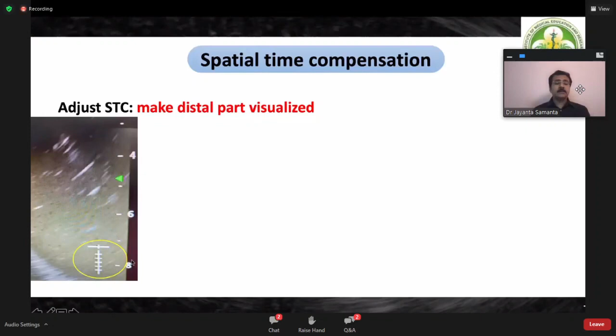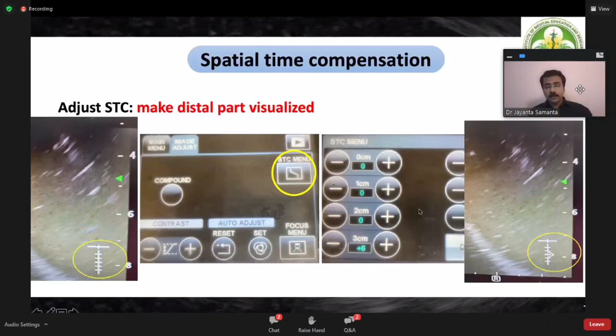So at default mode, you'll find something like this. At various depths, at 0, 1, 2, 3, 4, 6 centimeters, the setting is kept at 0. Let's say we want to visualize a deeper tissue and want to enhance the image that is getting reflected from the deeper tissues. Then we go to this STC menu, the spatial time compensation menu. You will find various depths mentioned. So let's say we find that there is a lesion and we want to better visualize that lesion, but it is at the level of 3 centimeters or 4 centimeters. Then what we do is we increase the STC compensation over here, and you'll find that at 3 centimeters there is an increase in the amplification of the reflected waves. So that will help in better visualization of the tissues at that level of the image.